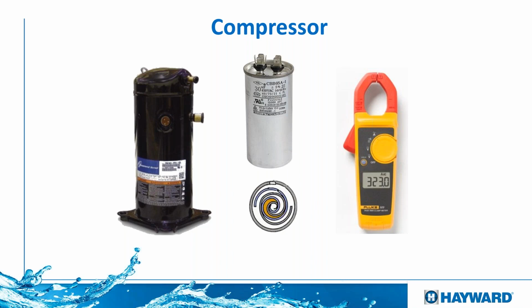If for some reason the capacitor is good, but the compressor still won't start, then we have to check the connections. You can see here the connections where the plug comes in. It's got 3 little pins. We want to make sure they're not corroded or burned or melted. If everything looks good, then we can check and make sure that the compressor is not grounded. To check this, we need a meter set to continuity, and then we go from ground to each one of these pins. If we have continuity with one of those pins, we know that compressor is shorted out. It's bad, it needs to be replaced. It burned out.